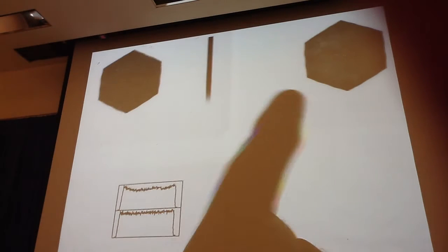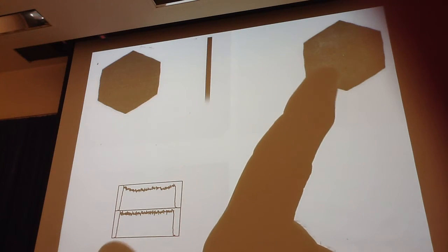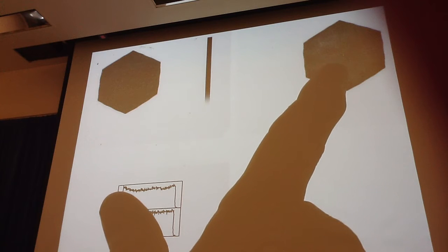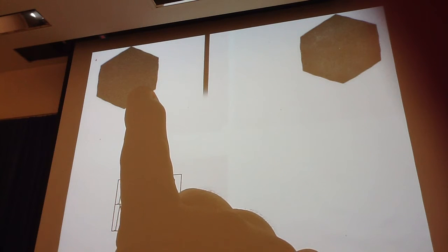So in this picture here, this is your one picture that you need to have to show that you don't have any major problems. Because what will happen, if I had a burned out PM tube or something on this image, on the corrected image, the computer would fill it in. So if all you ever did was corrected pictures, you're not going to see any problems with your camera.